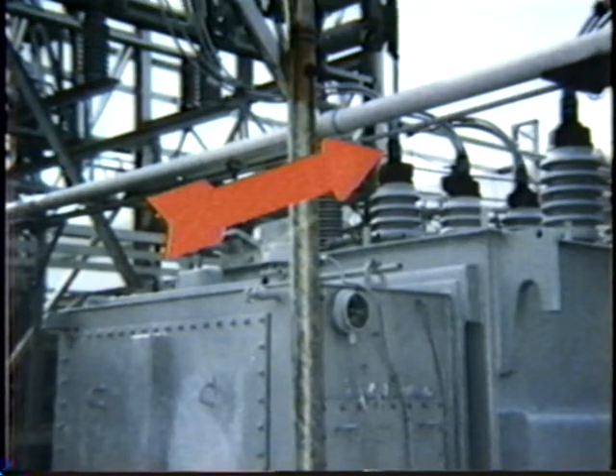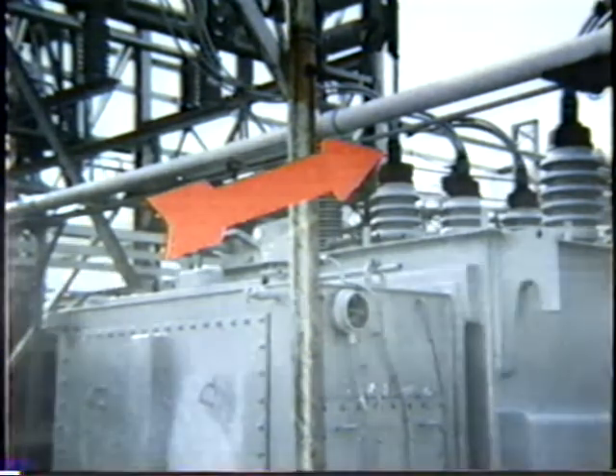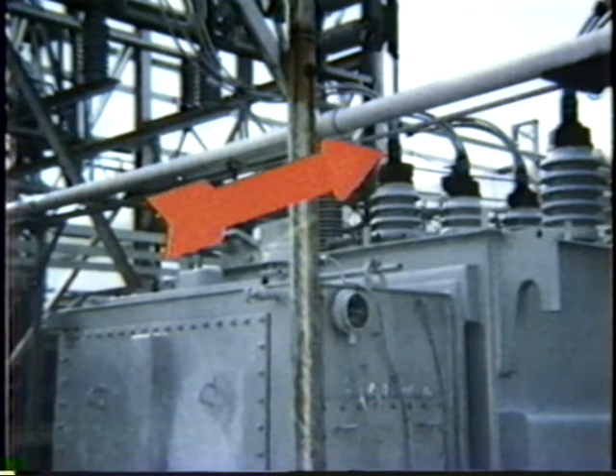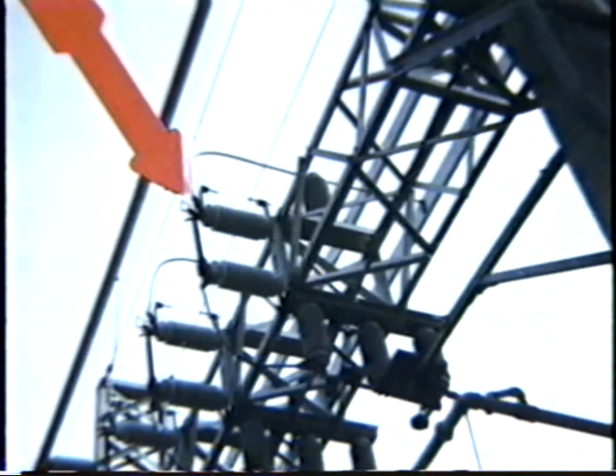Now, let's look at some larger equipment, such as this transformer. A failure here might interrupt power to a great deal of equipment. Under infrared, we find evidence of a bad connection. Again, we are looking at major electrical supply equipment. And again, we see evidence of a bad connection. Infrared photography not only provides another way to look at equipment and forecast problems, some insurance providers have come to recognize the value it has in terms of safety and fire prevention.